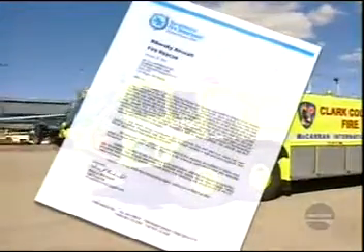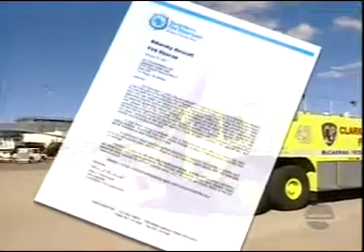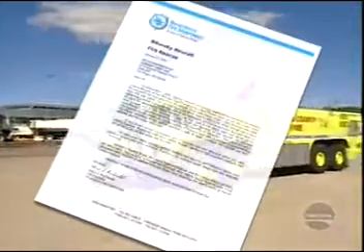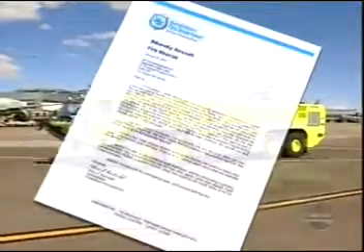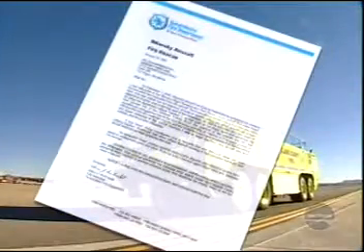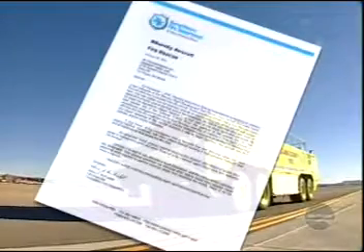It was found during investigation that a hydraulic line and electrical wires had been rubbing together. Eventually, both lines rubbed through, causing a high-pressure hydraulic leak and an electrical arc that ignited the fine mist. By using your clean product, minimal cleaning was required, and millions of dollars were saved in replacement parts and labor. Foam or a dry chemical agent would have only extended the damage.